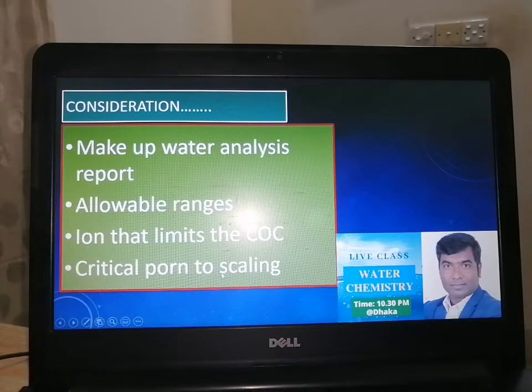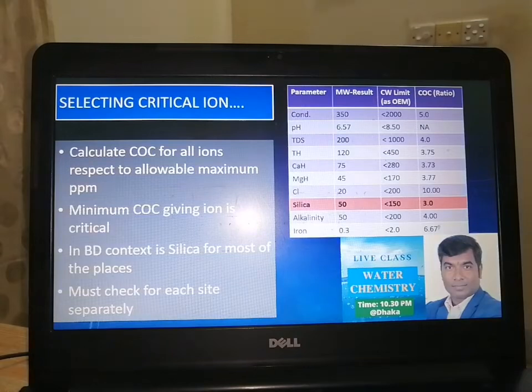So what do we do to select the critical ion? This chart is very important. Once I have the makeup water analysis and the cooling water allowable limit, I'm considering cooling water here to measure the cycle of concentration and understand the critical ion.